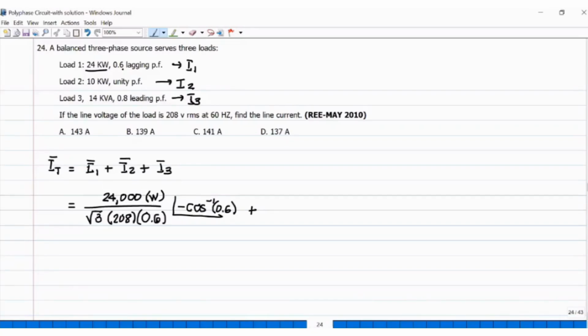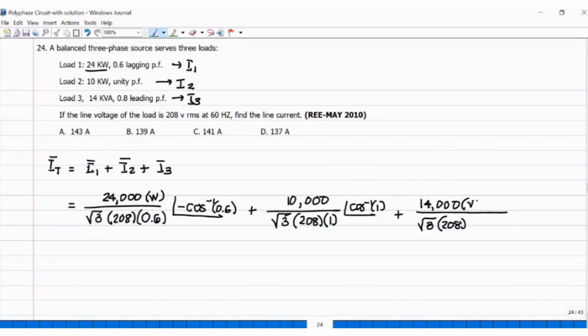Then yung I2, 10 kilowatts, unity power factor, so divided by square root of 3 times 208 times 1. Ang angle niyan, arc cosine 1, which is 0. Plus 14 kVA, so that will be 14,000 over square root of 3 times 208. Kailangan pa bang i-divide ng power factor? Hindi na, bakit? Kasi naka-volt ampere na to.